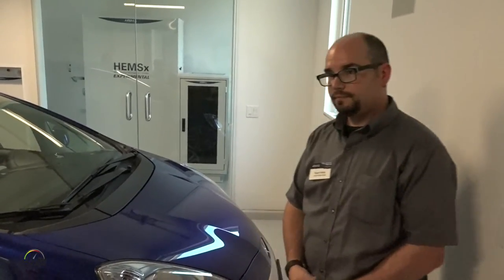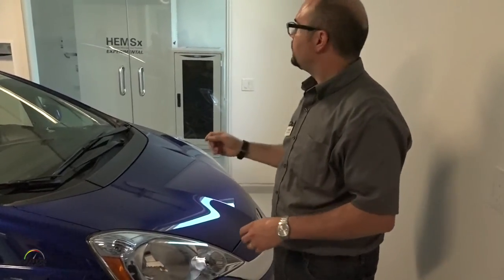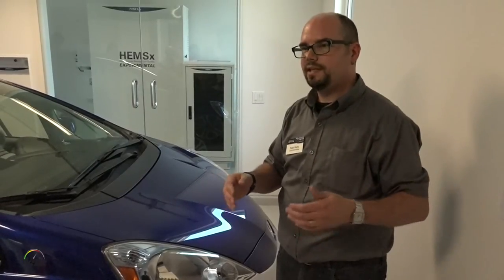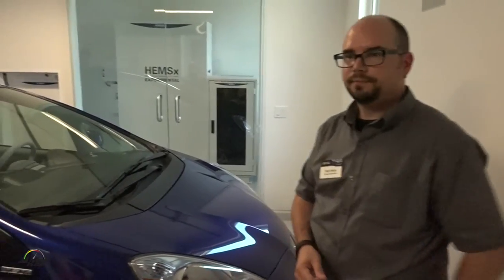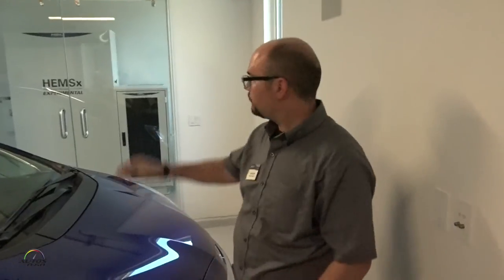There is a time when the system does convert to AC. The device has an AC inverter — that's actually what you can hear switching right now — and it's currently pushing power onto the grid because the house isn't using as much power as is being generated. All the lights and the heat pump are AC equipment, not DC, so you have to convert to AC to get it up into the house. DC distribution isn't commercially feasible yet in terms of buying UL-listed equipment an electrician can install. And to send power to the grid, you have to convert to 240-volt AC.